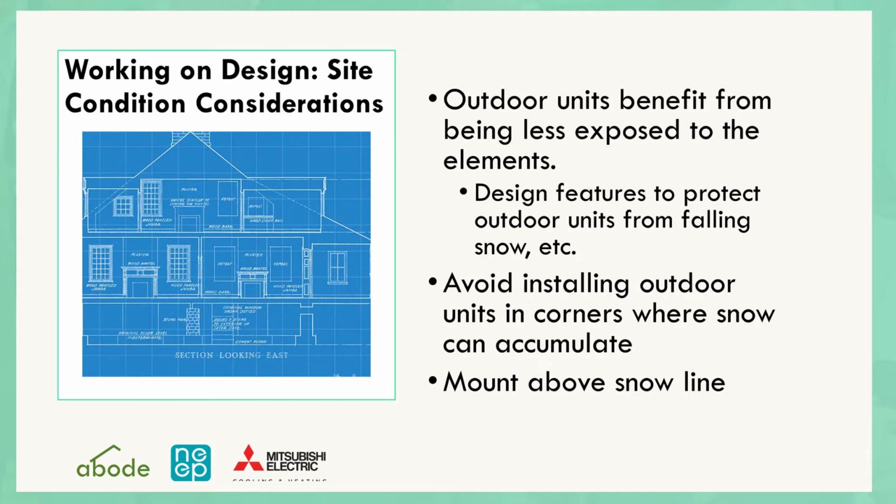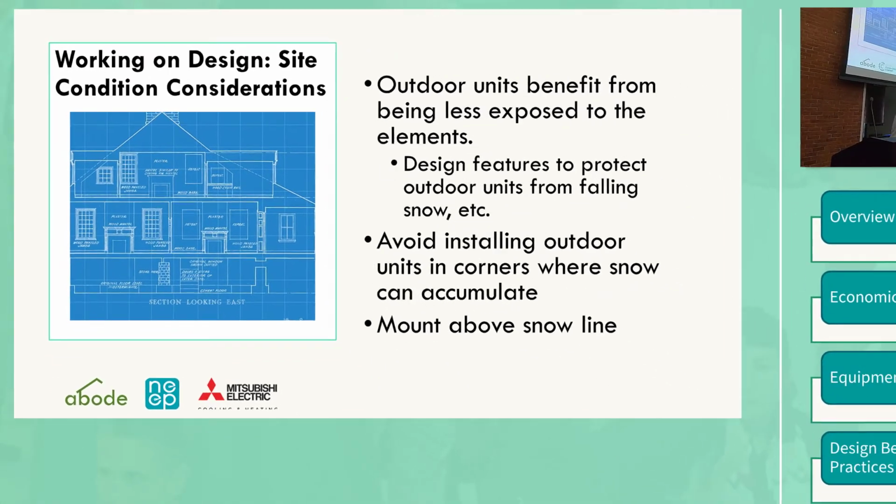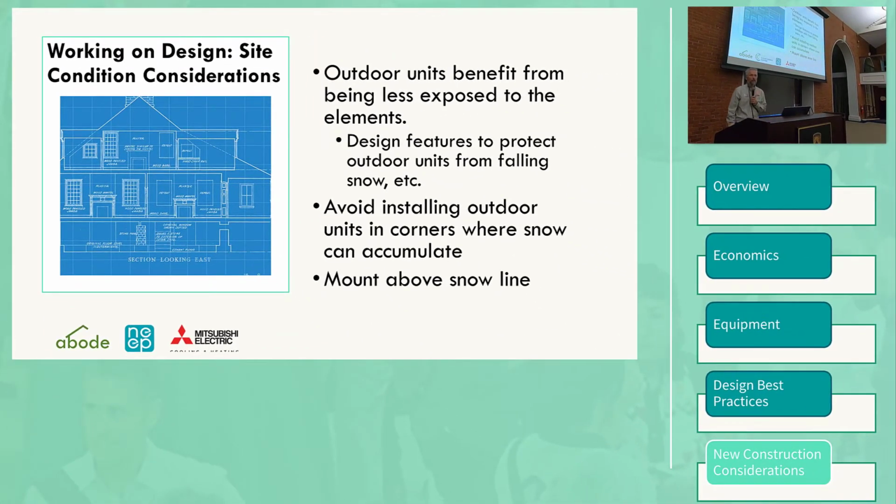Design considerations, whether it's one or multiple outdoor units. I would recommend that if you use brackets for mounting the outdoor unit to the side of the building, you use a bracket that comes along and then has another little jog and lags into the concrete, as opposed to the wall of the outside of the house. My unit is mounted to the side of my house, and in the middle of winter when it scrolls up to full speed, I can hear it. It's not nearly as loud as the old lift pump used to be, but I can hear it. And so clients are going to have different levels of sensitivity to the noise that it can make.